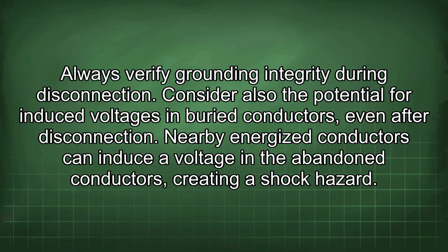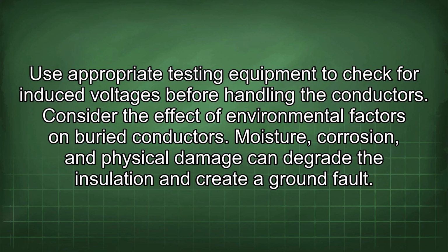Consider also the potential for induced voltages in buried conductors even after disconnection. Nearby energized conductors can induce a voltage in the abandoned conductors, creating a shock hazard. Use appropriate testing equipment to check for induced voltages before handling the conductors.